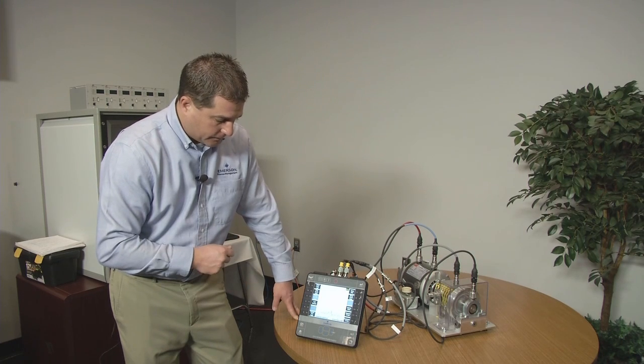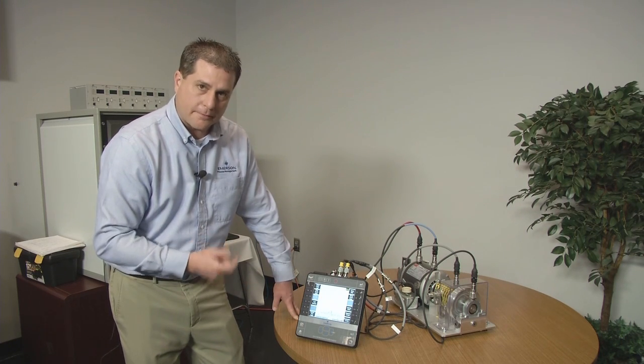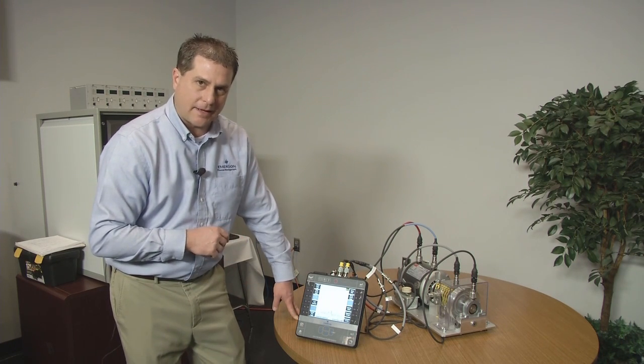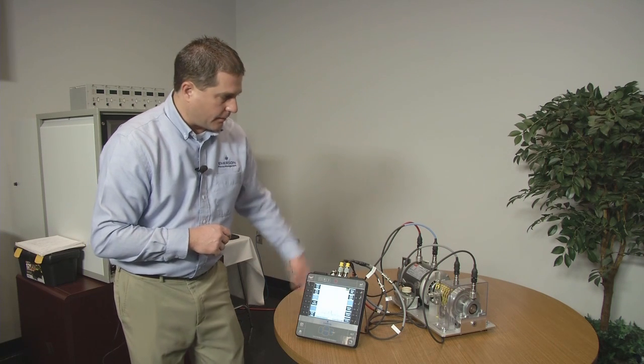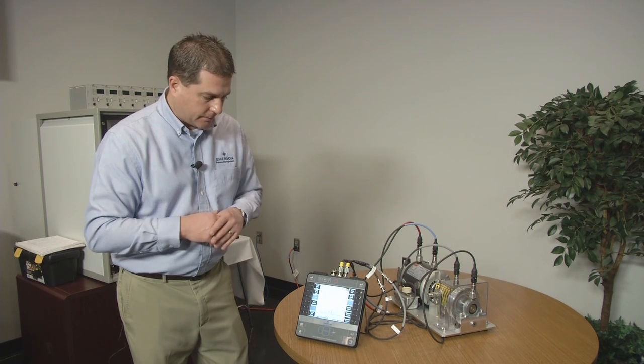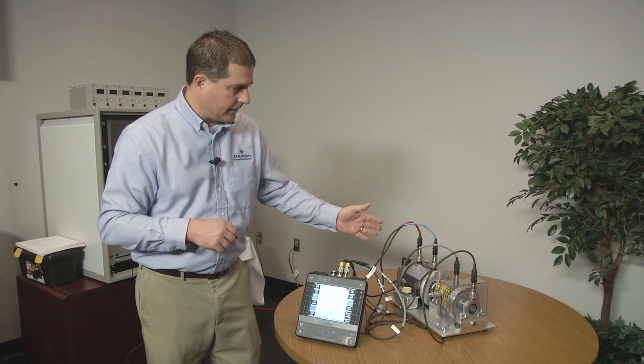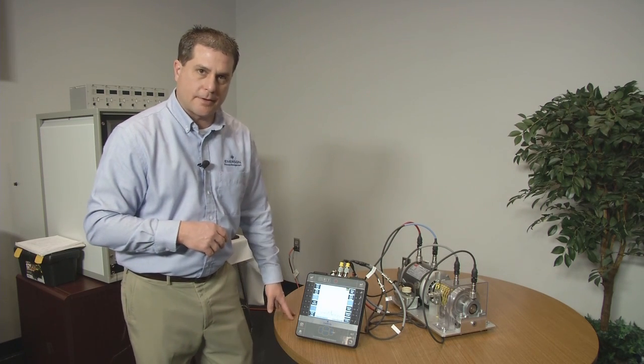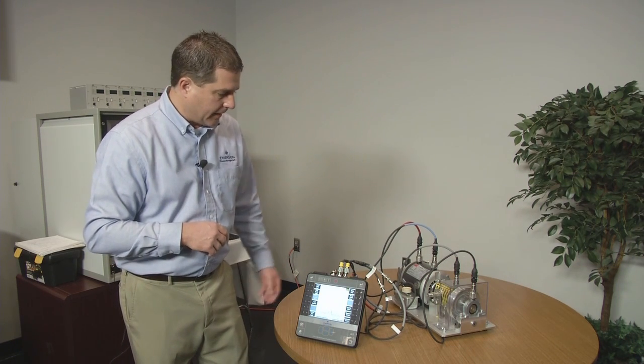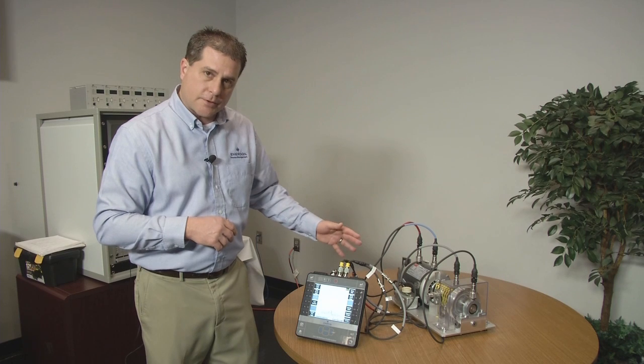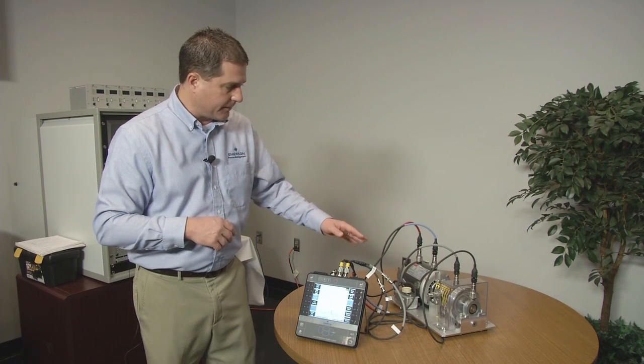Now what I can do to further verify that I think I've got a misalignment condition is cross-channel phase across a coupling is a good indication, a good test to run to show misalignment. If it really is a misalignment condition, then I should see 180 degrees phase shift across this coupling. And so this is where the four channel CSI 2140 comes in handy.